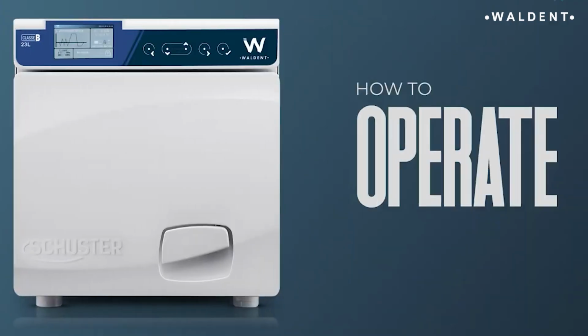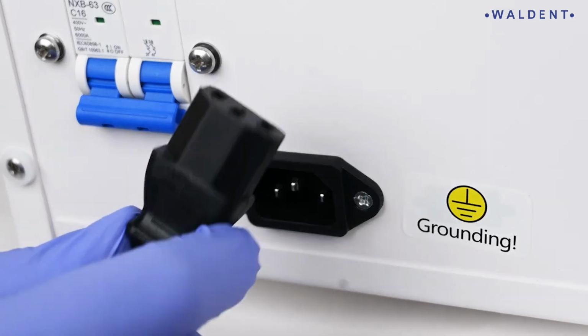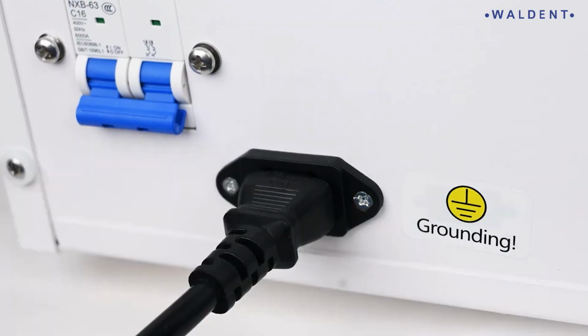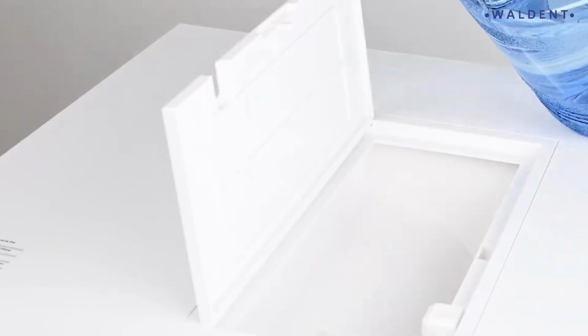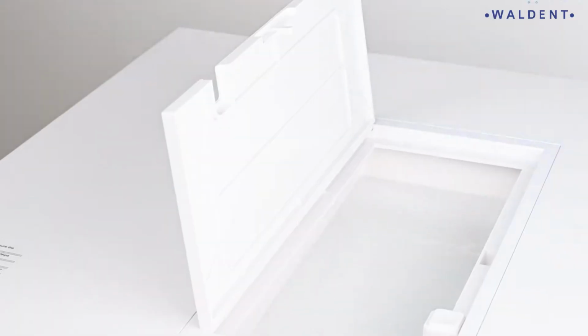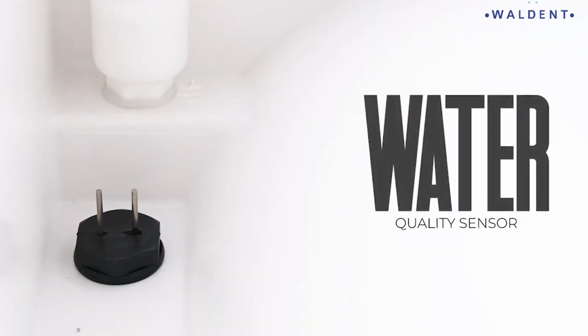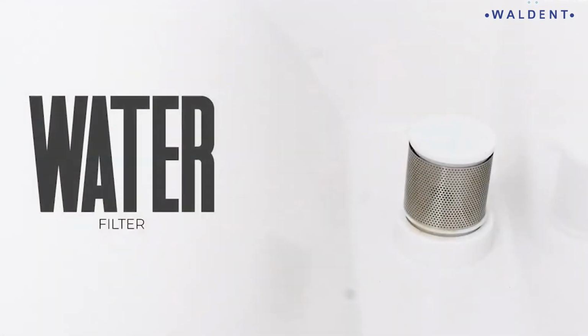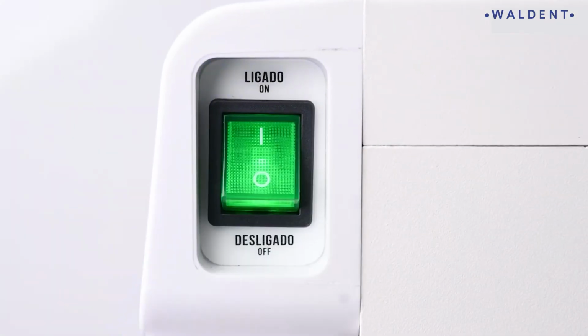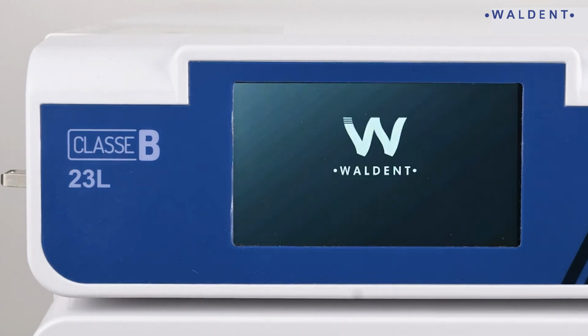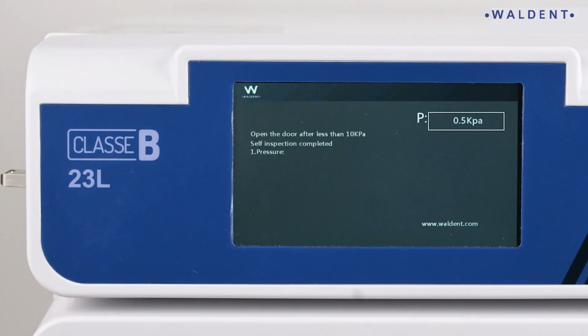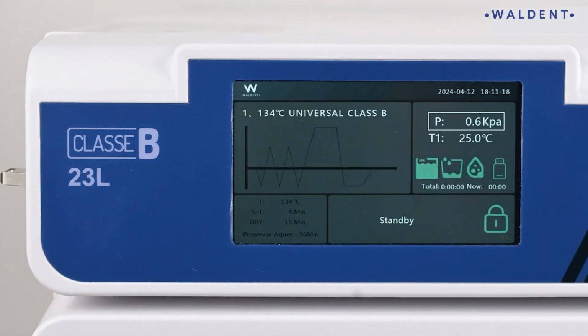Next, we'll explore how to operate and utilize Waldent Schuster autoclave effectively. Firstly, start by connecting the power cord to the power socket and switch on the air circuit breaker. Pour distilled water into the tank. In the tank, we can see water quality sensor, water level sensor and water filter. By switching on the power button, the unit will enter into the self-test mode, which takes around 10 seconds for self-testing. If the pressure value is more than 10 kilopascal, perform pressure correction. If the pressure value shows around 0 kilopascal, we can proceed ahead.